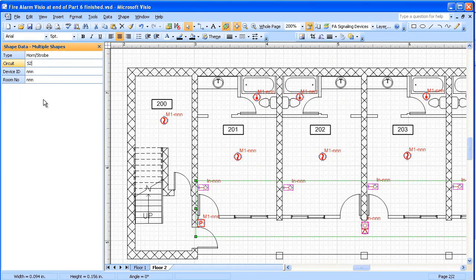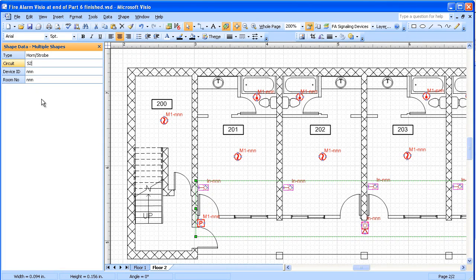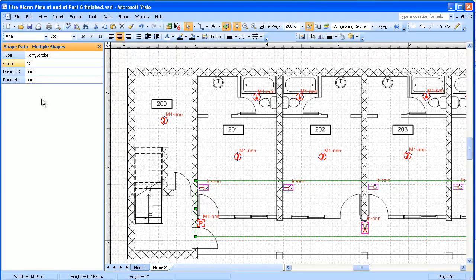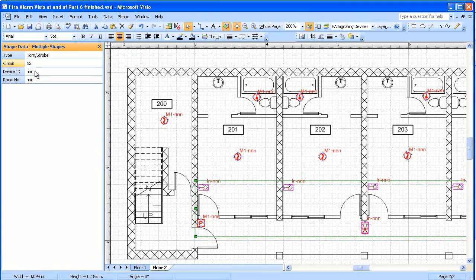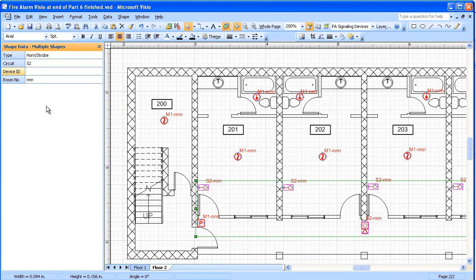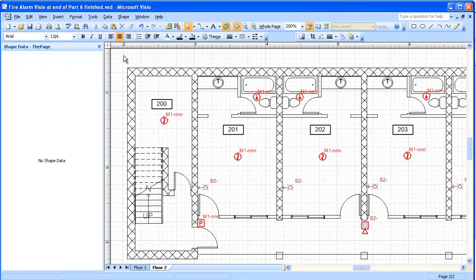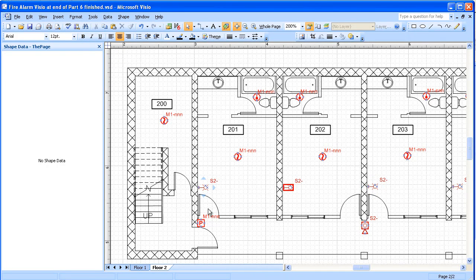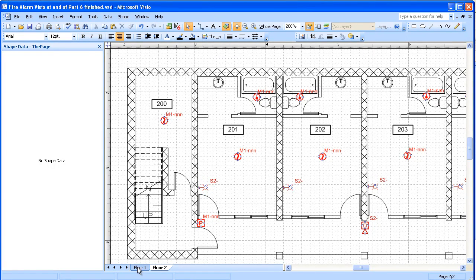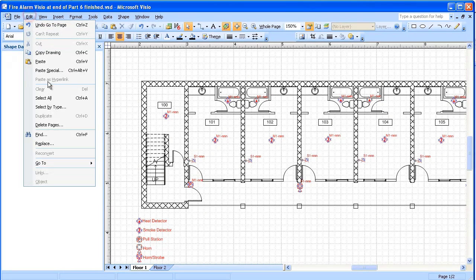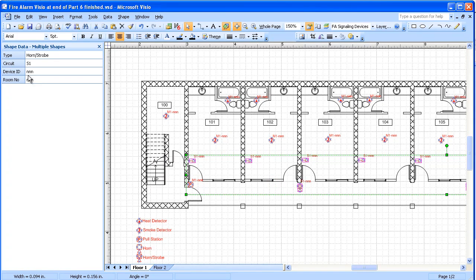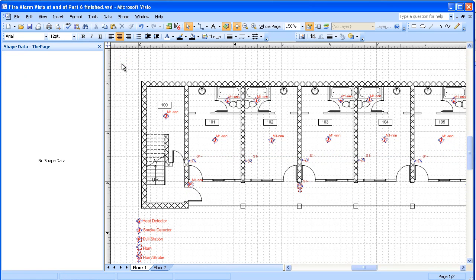And one other feature here is the fact that we're not going to have any device IDs on our signaling devices because they're going to be non-addressable. So I'm just going to go in there and delete device ID on my signaling devices. So you see how those signaling devices lost that part of the identification. I'm going to go back and do that same thing on my signaling devices on the first floor.